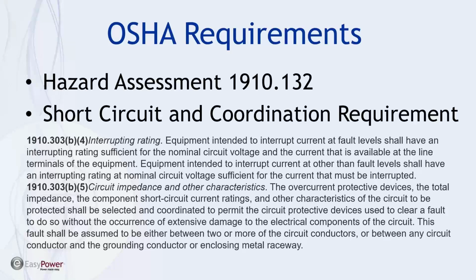The problem is that was in 1964. If the study has not been done since 1964, the fault current available from the utility is way different than it was in 1964. The loads have gone up, there's more generation, there's more transmission lines, more substations. It's all shifted, and now the fault current is much higher on the high side, which is going to have an impact on the low side as well. So now the equipment that was rated for the fault current is no longer rated for the fault current, and instead of holding up and tripping the breaker, it blows up. And now if somebody's there and they're not planning on having anything happen and it happens to blow up and they weren't fully protected with the level of arc flash protection that they need, it becomes a problem.